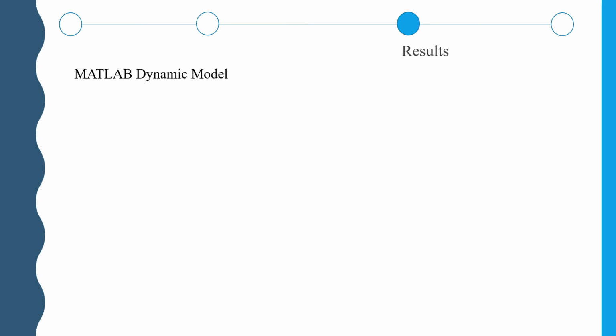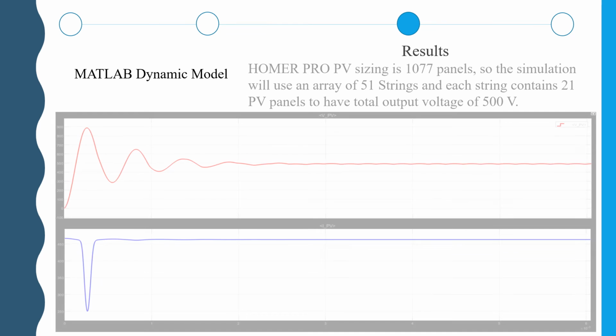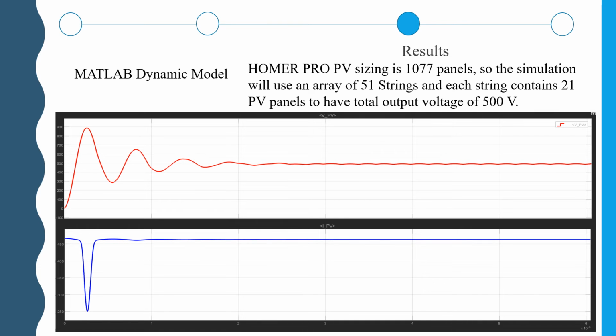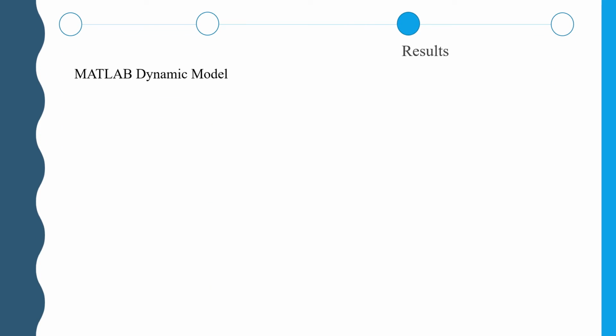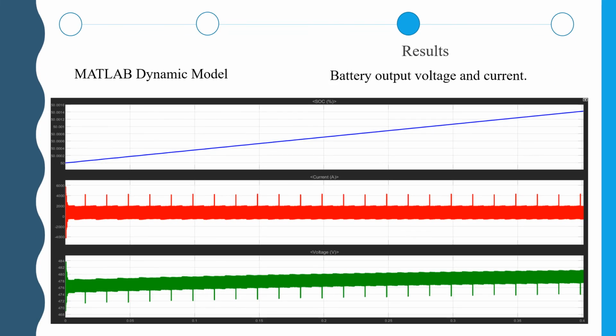In this part, we will discuss the final results of the dynamic simulation, which is done by Simulink. Homer Pro PV sizing is 1077 panels, so our simulation will use an array of 51 strings, and each string contains 21 PV panels to have total output voltage of 504 volts in steady state and after the transient response. Also from Homer Pro, the array of batteries consists of 28 strings and each string contains 40 batteries.